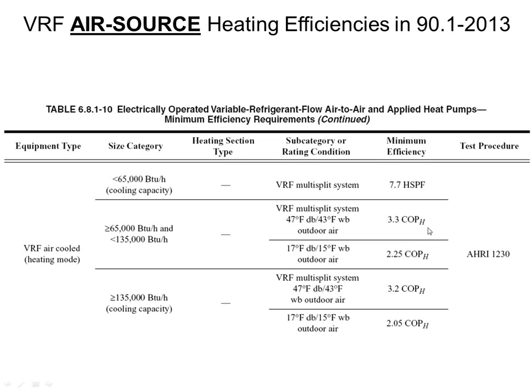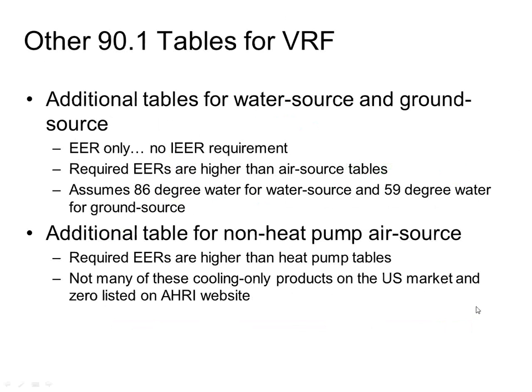And you're going to find that for a lot of these systems. It'd be really hard to find a system that does not comply with the ASHRAE standard. Most of them do. And you also notice there's fewer ranges here on the heating side that you have to hit. There's basically just 3 sizes. The small ones are rated in HSPF, although hardly anybody, I would argue maybe even nobody, makes a VRF system that's less than 65,000 BTUs, less than 5 tons, or less than 5.5 tons, so it almost never comes up, right?